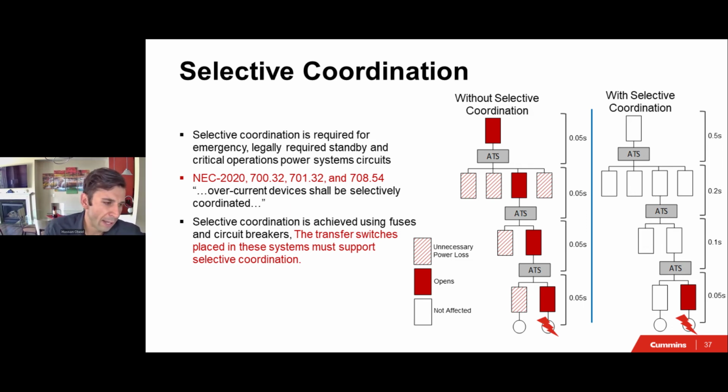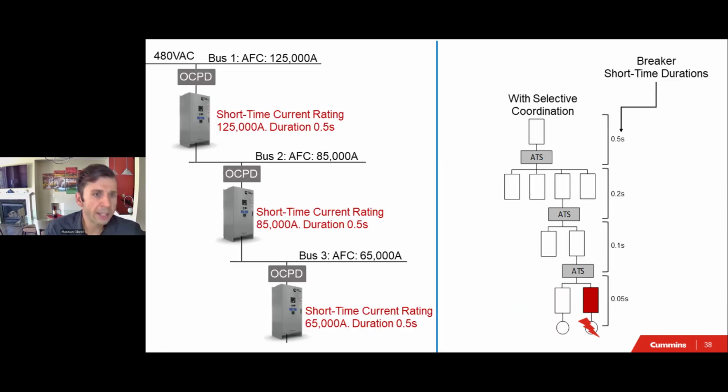So how do we apply the transfer switch rating that we talked about? Here, again, we're using the same example. We did the fault current analysis. We came up with 125,000 amps in one circuit. If we have maybe 85,000, maybe 65,000 amps, and so we have the transfer switch with the different ratings. We've talked about that. We selected the right transfer switch with the right WCR.